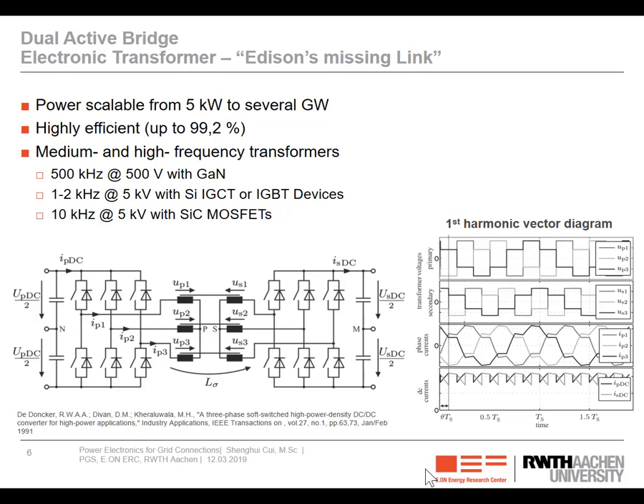Such a converter can be scalable in power rating from several kilowatts to several gigawatts, and it is highly efficient. In accordance with our calculation, it can be as efficient as 99.2%. The operation frequency of the transformer highly depends on what kind of material we are using for the transformer core and these devices. For low voltage applications like 500 volts, when we are using gallium nitride devices, we can realize transformer operation at 500 kilohertz.